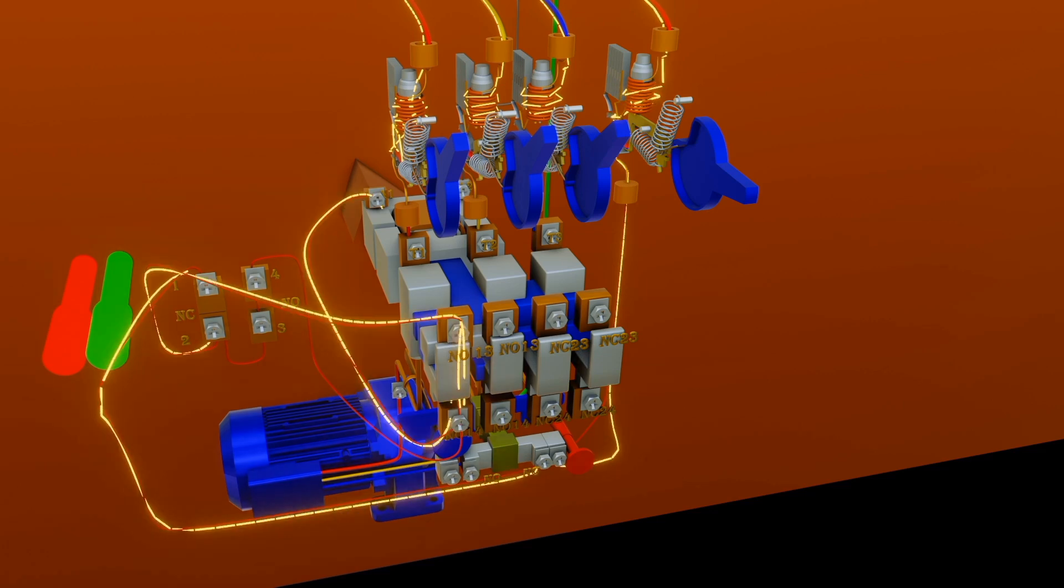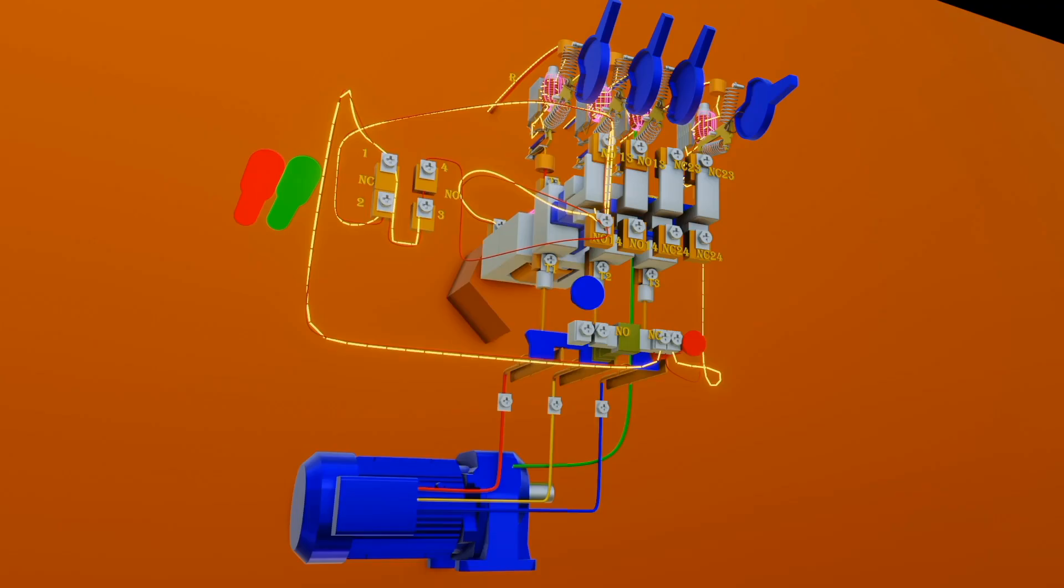But even when push button becomes open after pressed, the flow of current will continue to the coil. That is from terminal 2 of push button to terminal 13. Remember, normally open 13 and 14 become closed, hence current reaches A1 of the coil. But once the stop push button is pressed, it will stop the current flow to the coil.